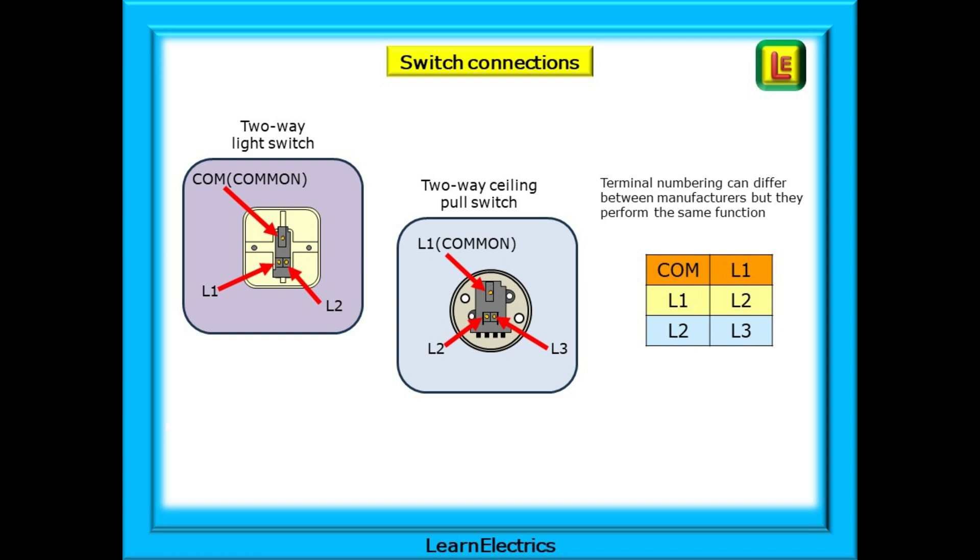Terminal numbering can change between manufacturers. Some will label the terminals as COM or common and L1 and L2. Others will label them as L1, L2 and L3. The little table shows the relationship. If your switch only uses one, two and three then the common is the L1 terminal.